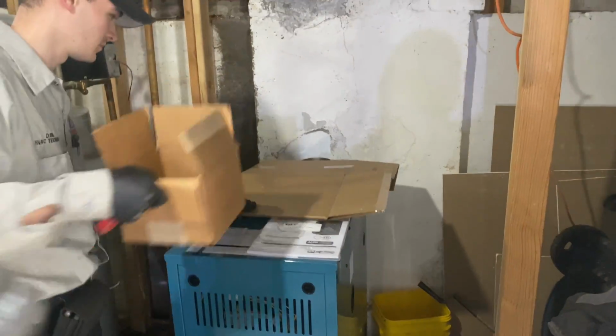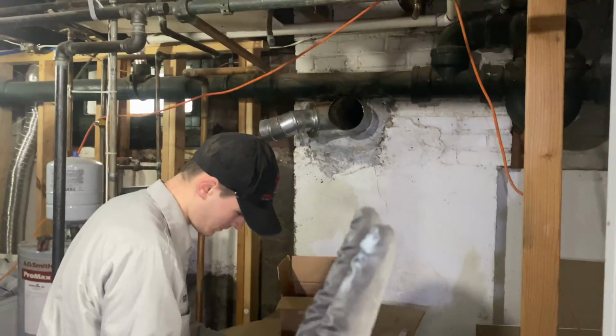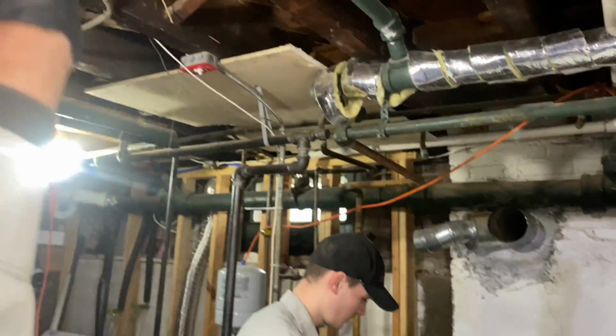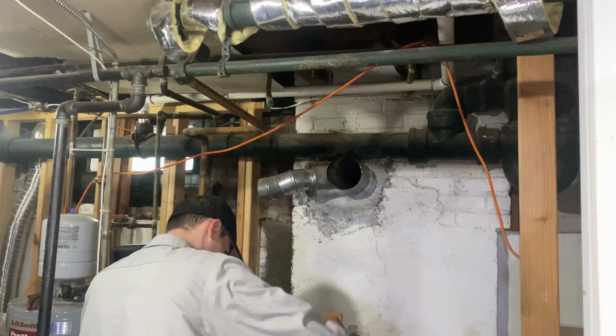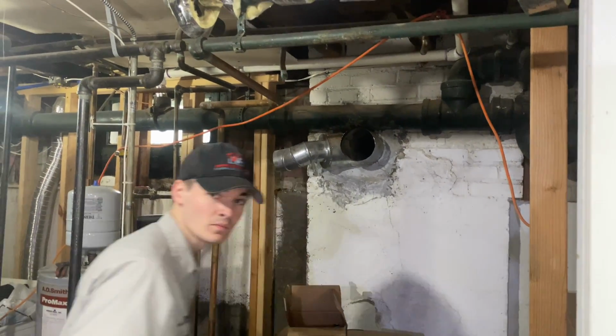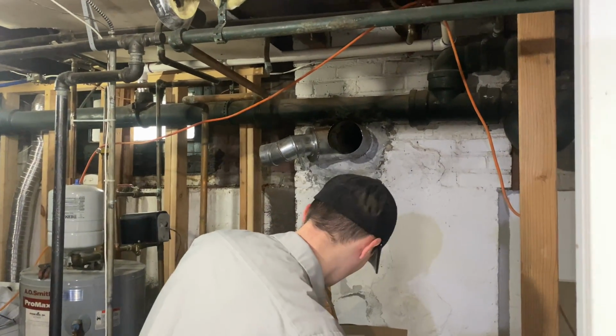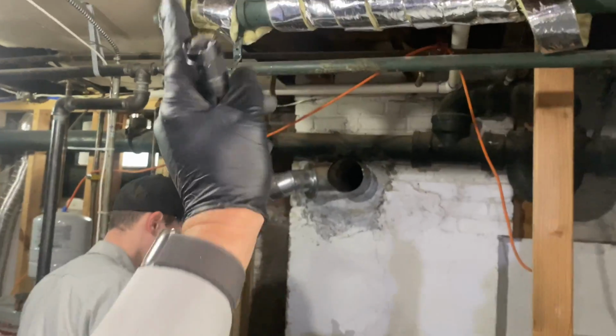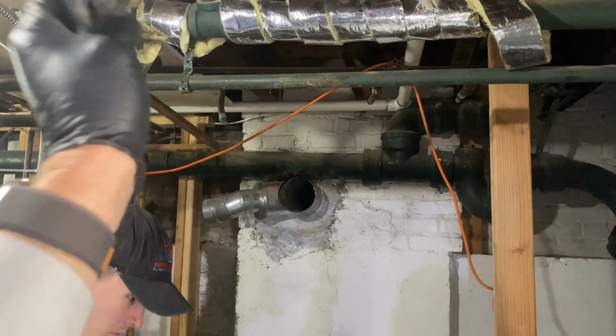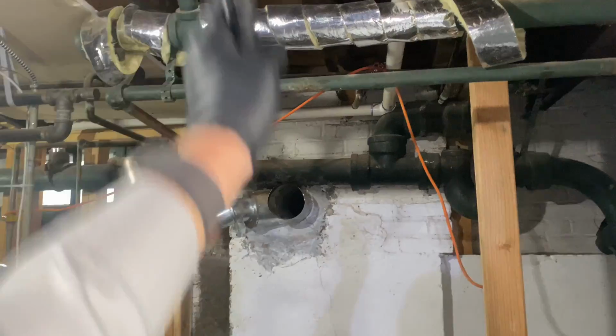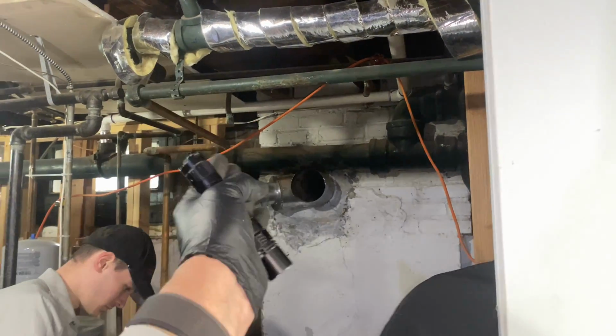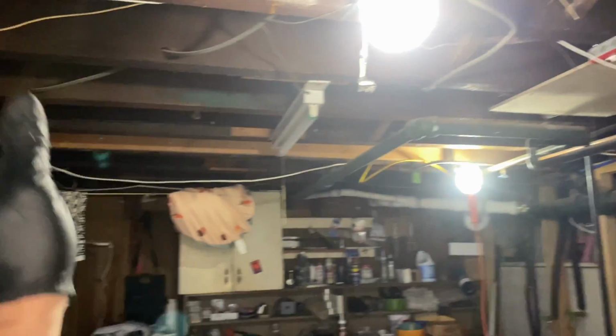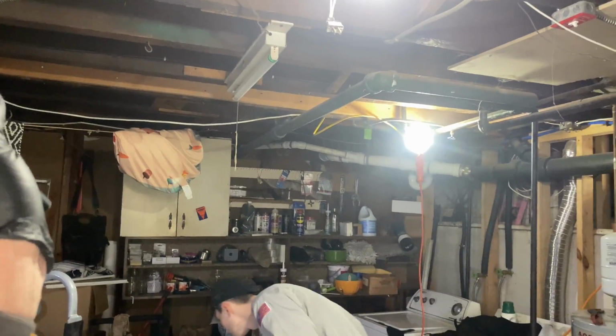Now, years ago, when I first got into the plumbing industry, the rule of thumb was if I had a chimney on the interior of the home, we did not need a stainless steel liner. That is no longer true. For this particular example, we have 3 exterior walls of that chimney exposed. You have to have a liner. Back in the days, inside chimneys didn't have to have a stainless steel liner, but now they do.